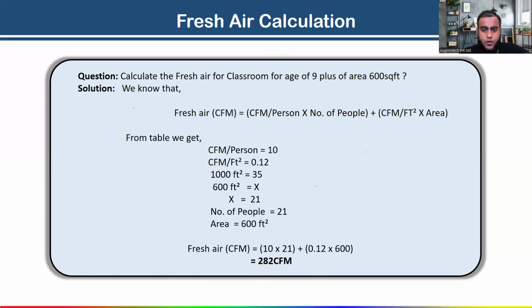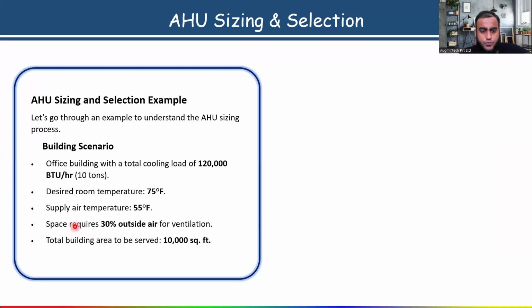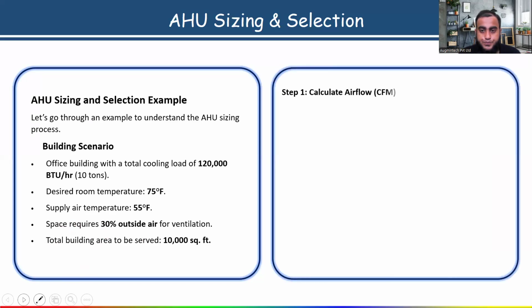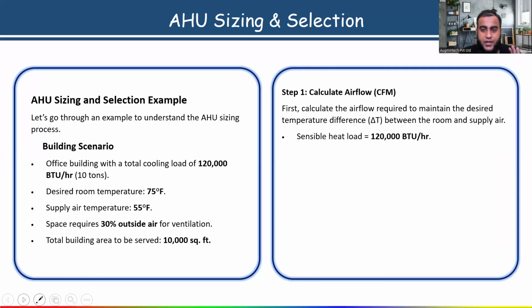Now come to our main topic, which we are discussing. Here I am assuming 30% outside air for ventilation, let's say, and the total building area is given. Now, can you tell me what the first step is? Calculate the airflow CFM by using the formula, simple. That formula I have already discussed. Here the sensible load is 1,20,000 BTU per hour. When you substitute this, what is the temperature difference? Have all of you understood now?